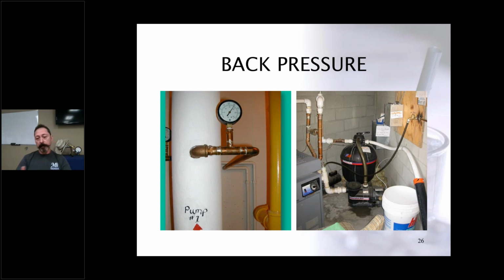So the picture here shows a hose connected to a swimming pool. That swimming pool is recirculating at, let's say, 30 PSI. The incoming supply pressure at the hose bib is, let's say, 60 PSI. But if that system pressure drops at the hose bib below 30, then the pool will simply be emptying into the distribution system, along with backwashing the filter and the sewer connection that you see there. That can also impact the water quality.